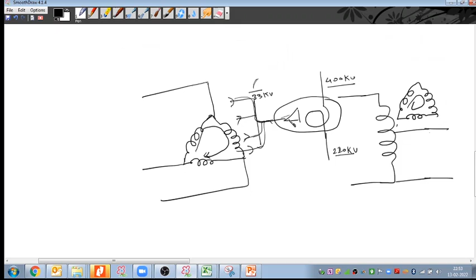So basically, on this 33 kilovolt side, we use all these equipment right now. All the power electronics come on the delta side here. It is not fed by this winding. So here we have the source of the power electronics switching that may produce the harmonics, third harmonics or multiples of the third harmonic, and that is going to enter here. So here we are putting in the delta. Okay, now it is clear.